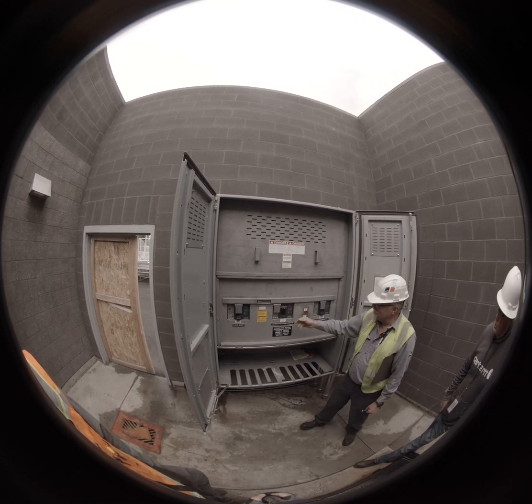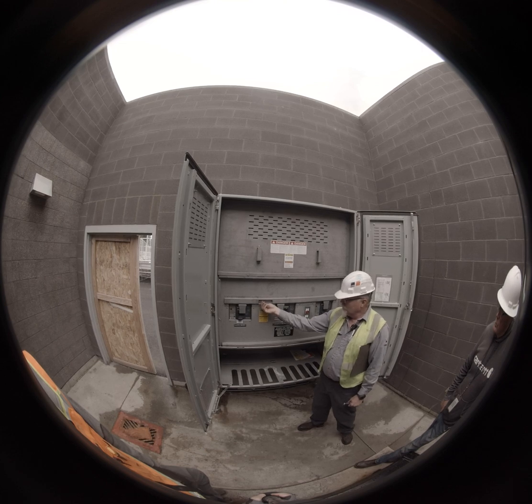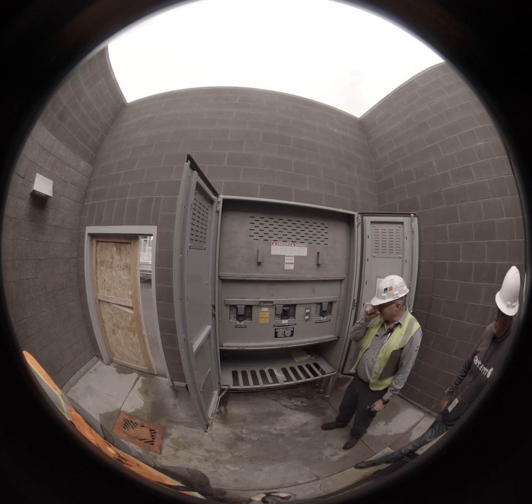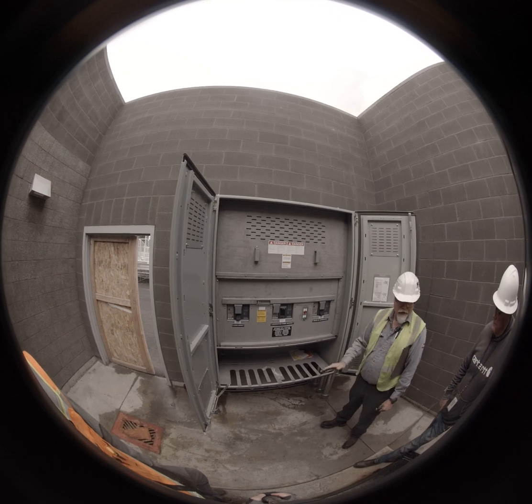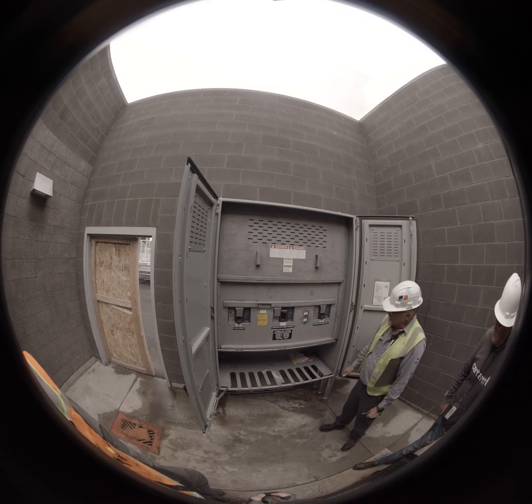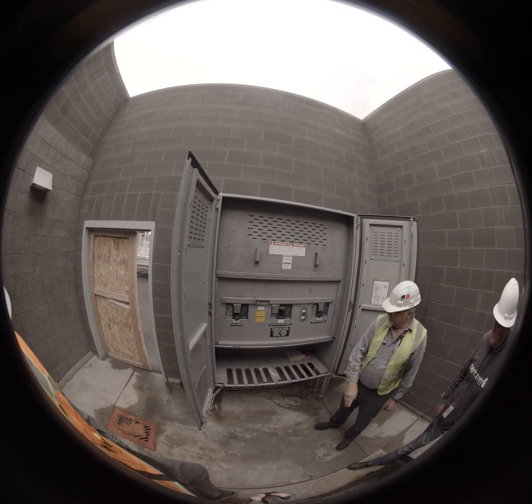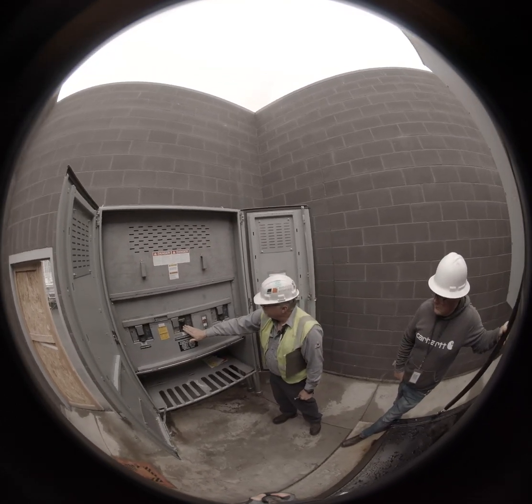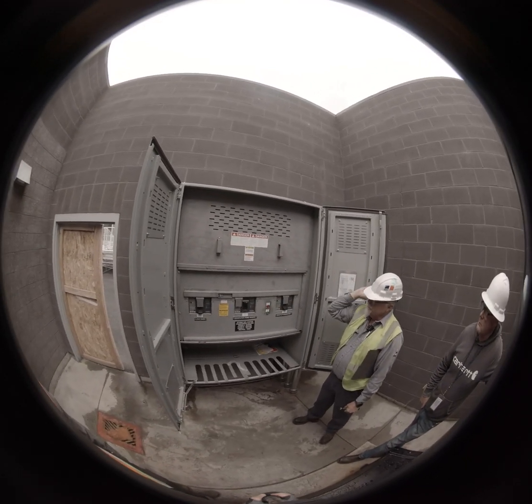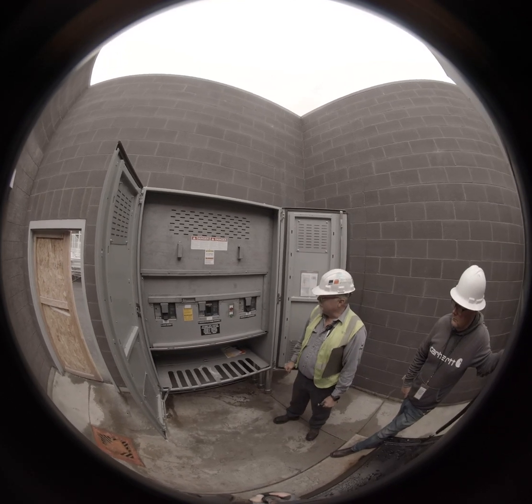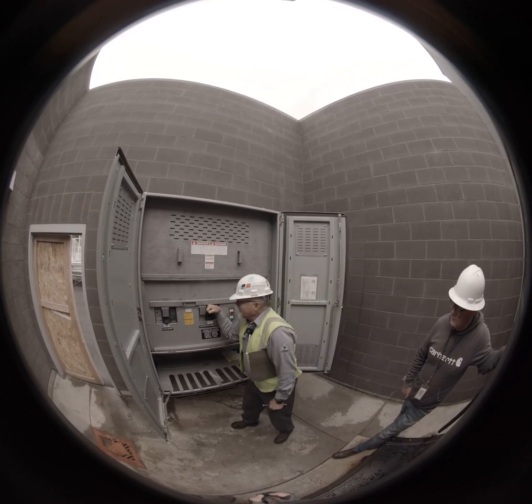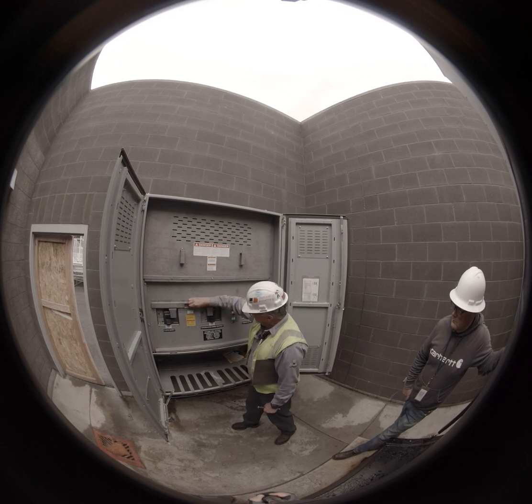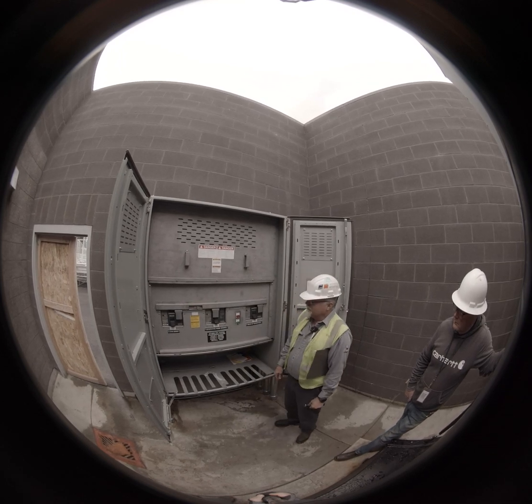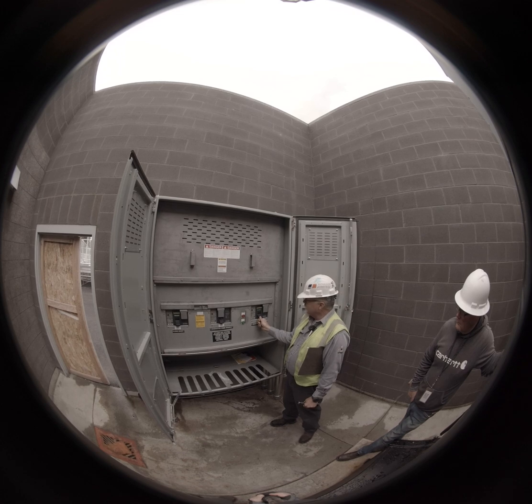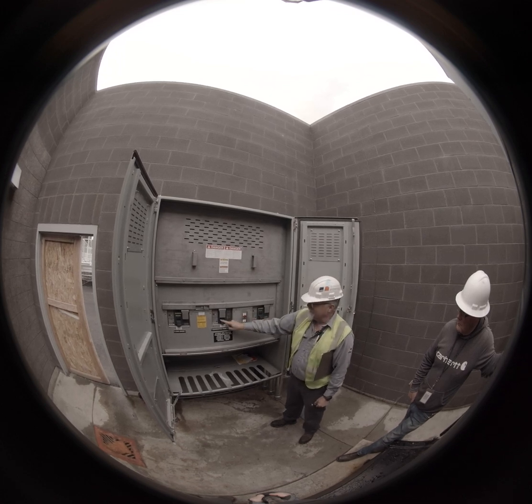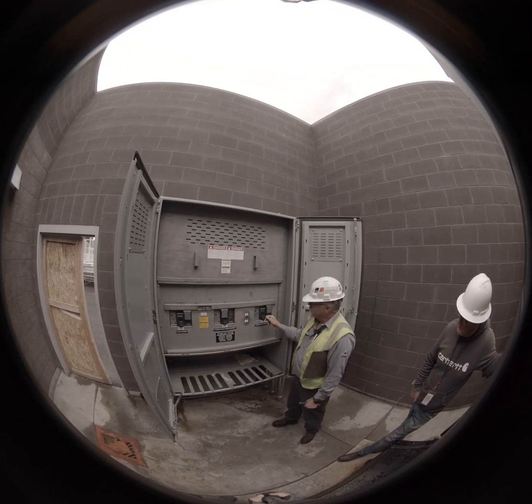You have a slider bar system on this, which will not allow operations, depending on where you're at. So normal operation, power comes from the generator set through this here breaker and goes into the 2 transfer switches that are sitting inside. You want a temp gen online? You can turn this guy on, but now you can't turn this guy on.